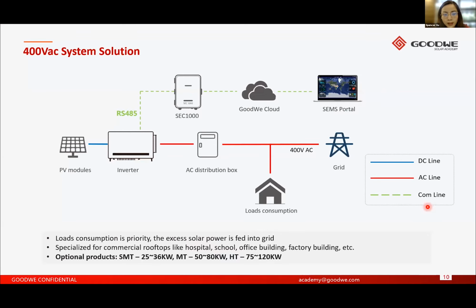Here, the most typical case is a 380 volt and 400 volt grid connection. The system is specialized for commercial rooftops. In this system, the generated solar power will be consumed by load first, and then the rest of the power will feed into the grid.